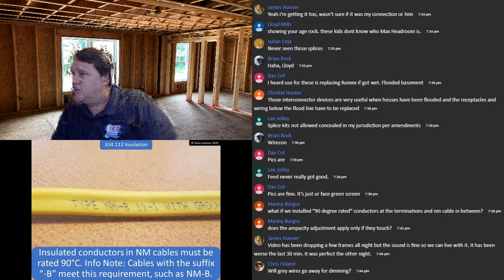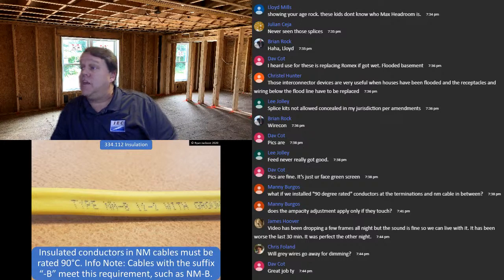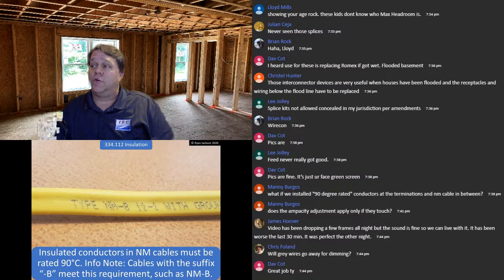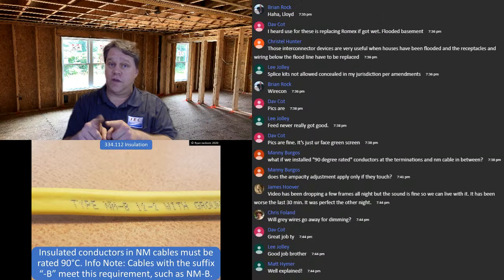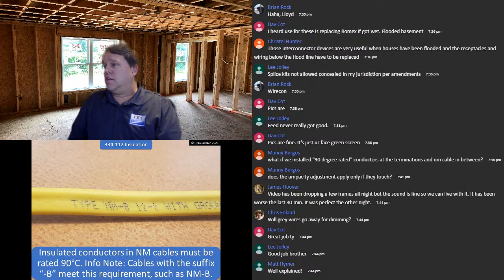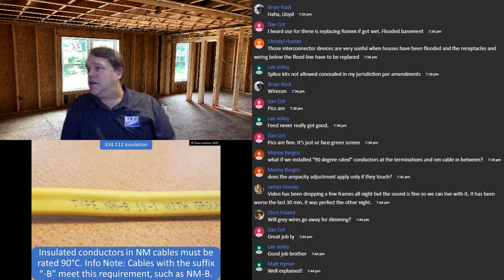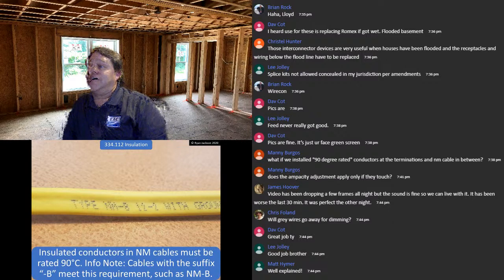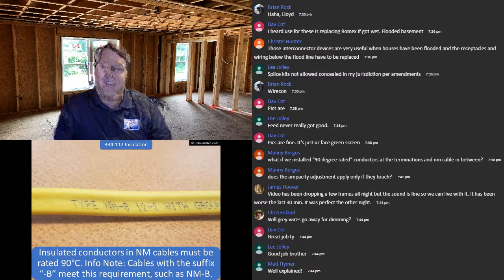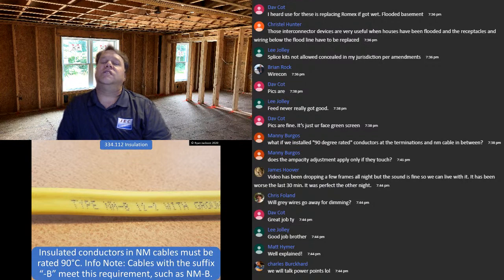Does the ampacity adjustment apply only if they touch? Manny, if you read 334.80, you will see that it is only if they don't maintain spacing. Thank you, Lee. Thank you, Matt. Thank you, Dave. Chris says, will the gray wires go away for dimming? Great point. Yes, they will. 410.69, I think, in the 2020 code.